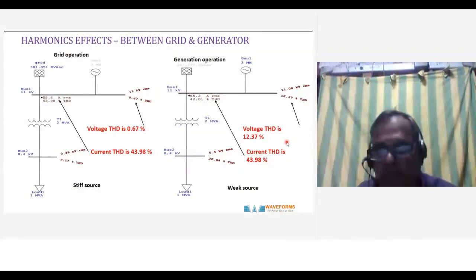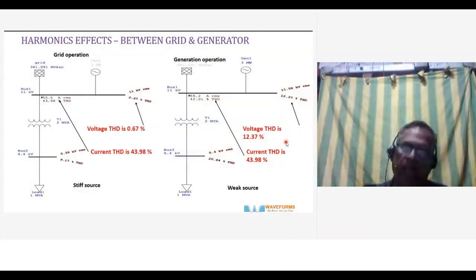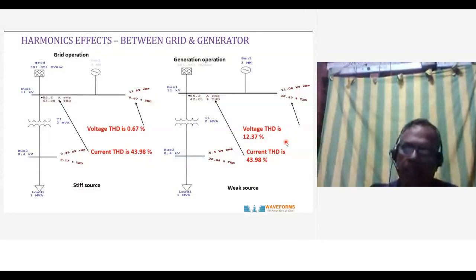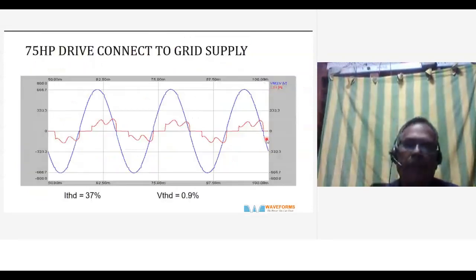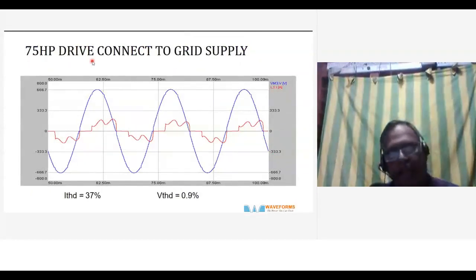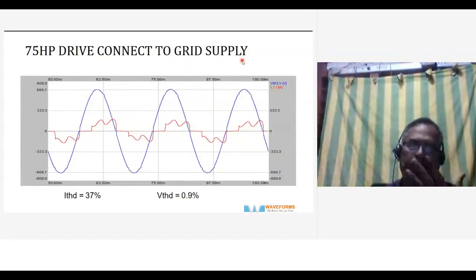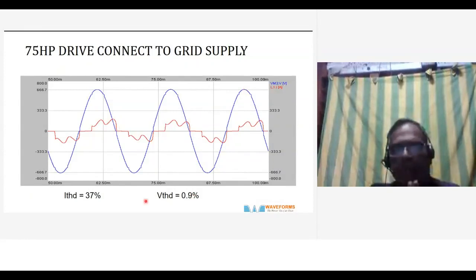So the current distortion, as it flows through the various impedances, distorts the voltage, and this voltage is fed to the other equipment. So voltage distortion is a serious problem when there is current distortion. Again, to emphasize the point, when you connect a 75 HP drive to grid supply, which is a very strong source with low impedance, the voltage does not get distorted. Can you see the blue? It does not get distorted. The current, which is in the red, is distorted. Voltage is not getting distorted.